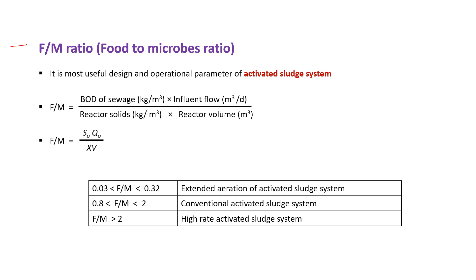The next formula is the F/M ratio — the food to microbes ratio — which is mainly related to the activated sludge system used for wastewater treatment. F/M = (BOD of sewage × influent flow rate) divided by (reactor solids × reactor volume). If F/M is between 0.03 and 0.32, the system requires extended aeration. If it is between 0.8 and 2, it is a conventional activated sludge system. If it is greater than 2, a high-rate activated sludge system is required.